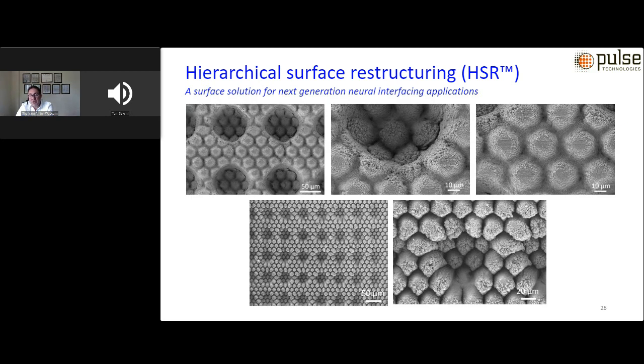One of the other benefits of the technology is that it can be applied on electrodes with existing surface texture or mechanically induced textures. Here you can see examples of a neurostimulation device electrode that was mechanically stamped in order to create dimples on the surface, which was subsequently restructured using our HSR technology successfully. You can see that the degree and the uniformity of restructuring is pretty remarkable on an electrode that is already mechanically textured. So that's an interesting aspect of the technology as well.